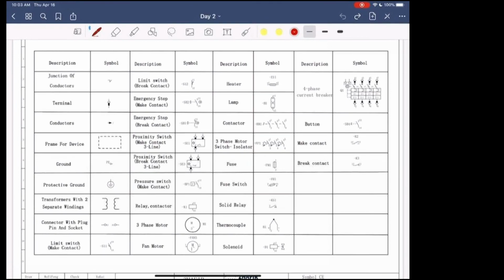So when you're reading the blueprints and you're looking at a contact that says, oh, this is a normally open switch, but I'm getting a reading, that's because the contact is in an energized position. And so therefore it does the opposite of what it's supposed to do.